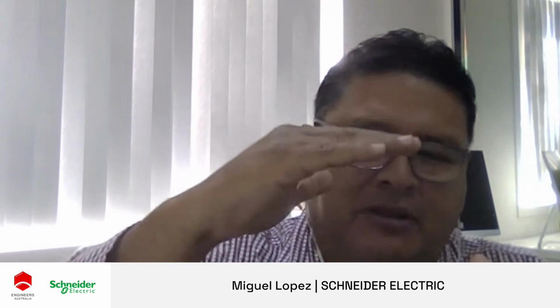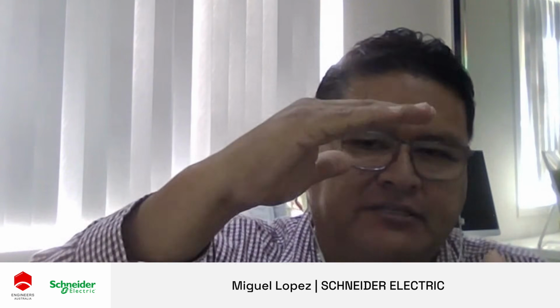Good question, thanks Ashok. For edge deployments, where you might have a couple hundred kilowatts in one rack, there's a rack-mounted CDU that takes up to 5U of space, mounted at the bottom of the rack. So it doesn't take up more space than you'd already have in a 1 to 300 kilowatt rack. We predict that will be more common for edge-type enterprise deployments. However, for large data centers, the AI factories NVIDIA talks about, you'll need a floor-mounted CDU.